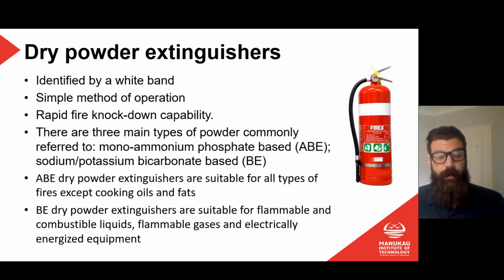It may put out the fire, but obviously water is a conductor, so what you're going to do there is pour water onto a live circuit, and that water that you pour on there is going to become live, so you're potentially creating another hazard. So although water may be an effective way of putting out an electrical fire, it's going to create other hazards, so we certainly don't do that either. Just be aware with the dry powder, if you're using that on an electrical fire, it's going to create a hell of a mess. That dry powder is pretty nasty stuff.